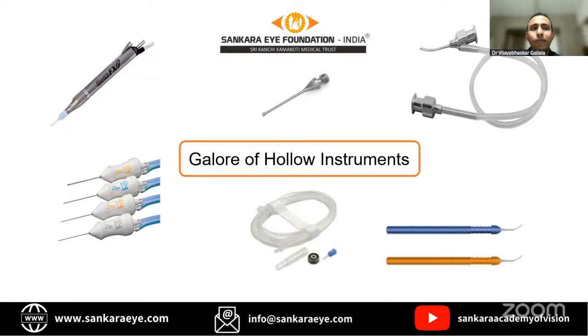Daily we use a lot of hollow instruments like phaco handpiece, tips, Simcoe, bimanuals, and vitrectomy cutters. So this small structure, complex design, fine instrument, hollow instrument makes the cleaning process and sterilization process very complicated.